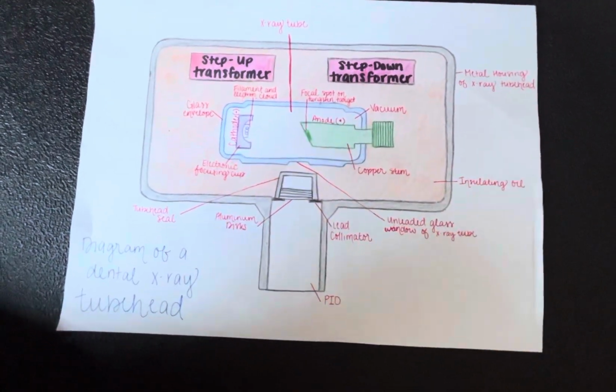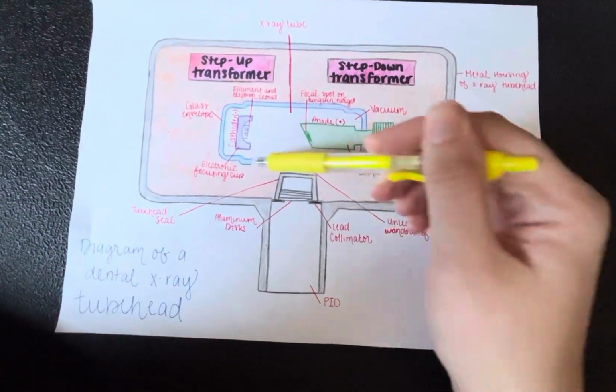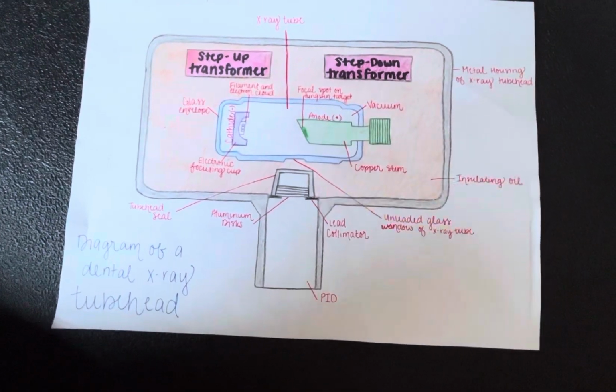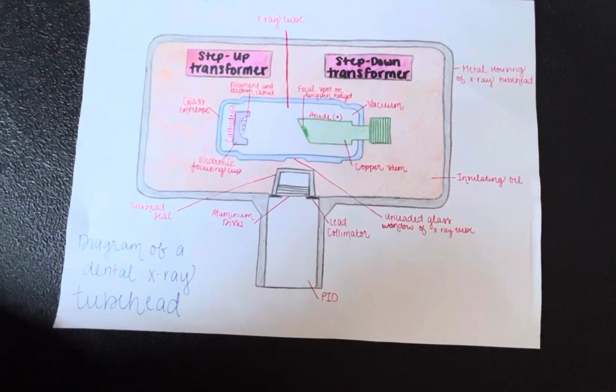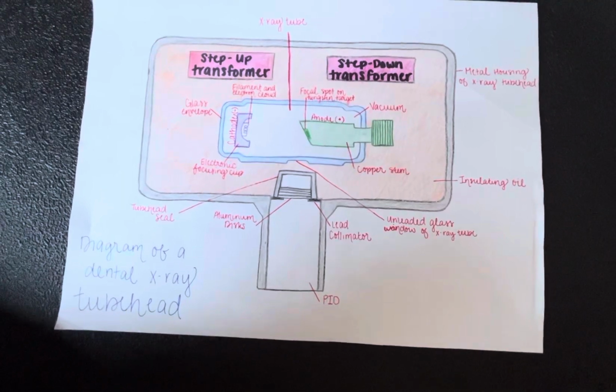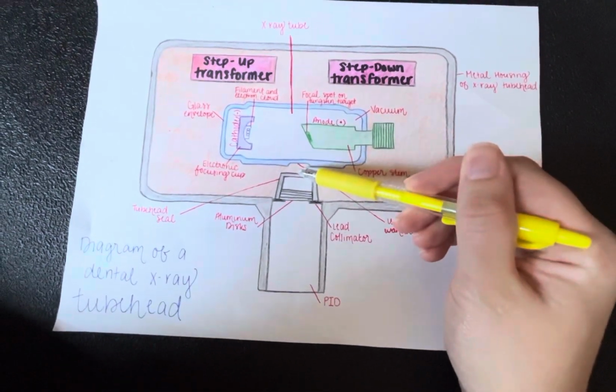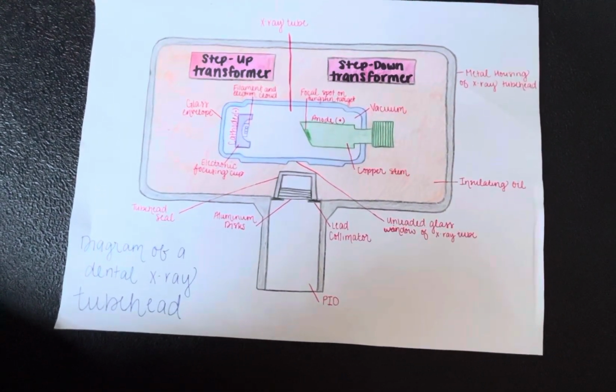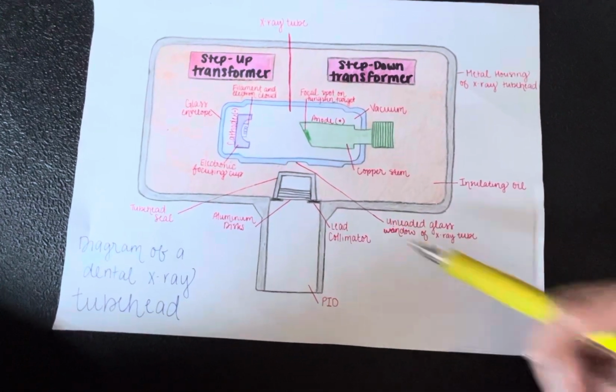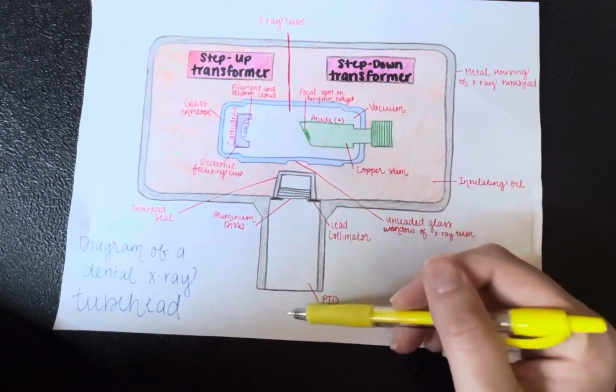Now let's talk about this X-ray tube. The leaded glass housing, or glass envelope, is a leaded glass vacuum tube that prevents X-rays from escaping in all directions. There's an unleaded glass window that allows the X-rays to exit the tube and directs them toward the aluminum discs, lead collimator, and PID.